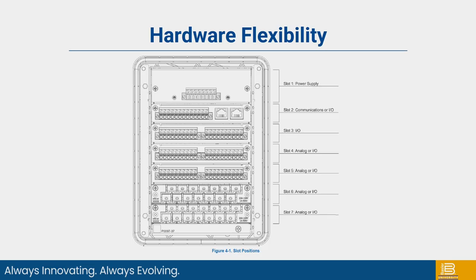This drawing here is the back side of the BE1-FLEX and the 7 available slots for different hardware. The power supply is always located in slot 1 at the top. The power supply also has an RS-485 connection along with an IRIG-B input for a satellite clock input for time sync purposes. Slot 2 can typically be a communication board with Ethernet communication, either fiber or copper via RJ45.